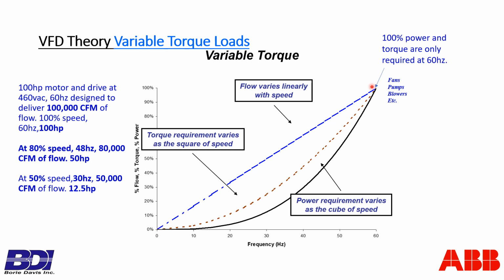The other thing you can see is, remember the constant torque equation, you had constant 100% torque available from 0 to 60 hertz because you needed it. This application, we don't need constant torque. It's variable torque. It varies at a square function, as we discussed on the last slide. It's the only place where we know you need full load or full torque is at 60 hertz. At any frequency below 60 hertz, the torque's beginning to drop off and the power required is beginning to drop off. So that's why I said if I can show you we can satisfy a constant torque load, surely you can see we can easily satisfy a variable torque load.